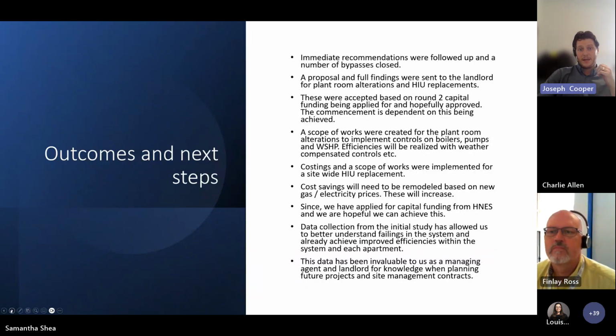As I said, the business case and economic case were strengthened by the potential funding, and the scope of works was created for the plant room alterations to implement controls on the boilers, pumps, and water source heat pump. Efficiencies will be realised with weather compensated controls and other measures—one key example being that, depending on the external temperature and the need for hot water, the temperature produced by the heat pump and distributed around the site will be higher or lower depending on needs.